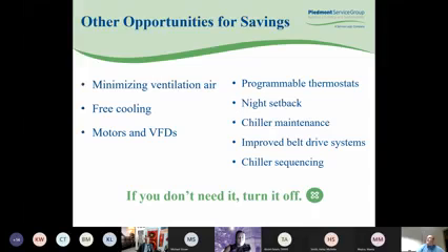Other opportunities include minimizing ventilation air. One of the things that has come about with COVID-19 is we've opened ventilation up to get as much outside air into a building as possible. By doing that, you're now heating or trying to cool air that is too hot in the summertime, and in the wintertime, you're trying to heat air that is too cold. So working on minimizing your ventilation air is very important right now.